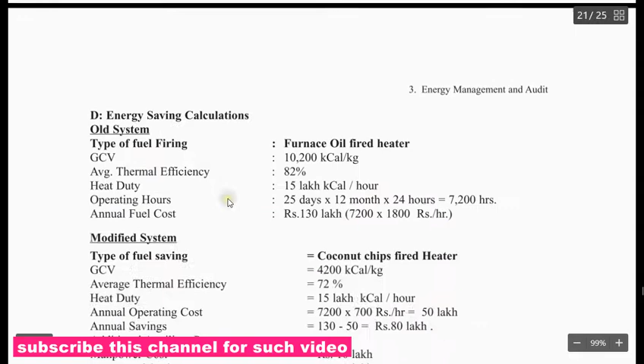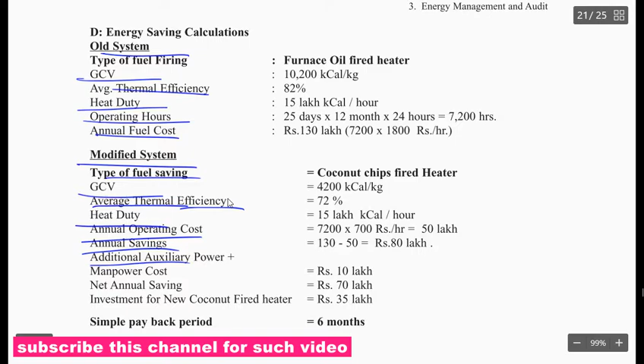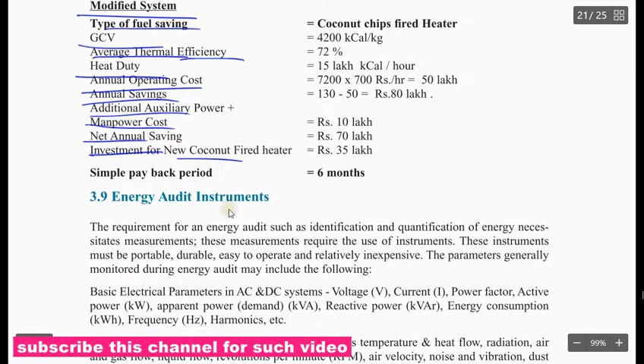And fuel energy saving calculation: old system, the average thermal efficiency, heat duty, operating hours and annual cost. And modified system: type of fuel, GCV, average thermal efficiency, heat duty, annual operating cost, annual saving, additional auxiliary power, manpower, net annual saving, and investment for the new coconut fired heater. And the simple payback period is 6 months.